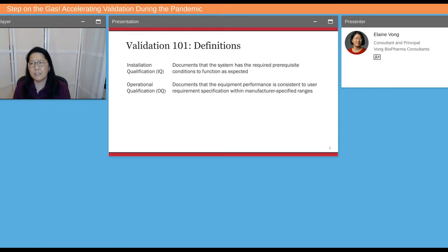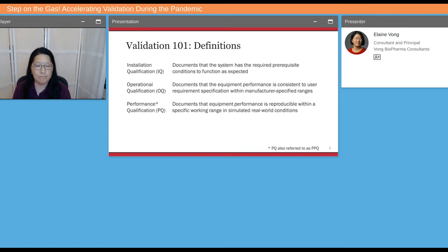It's always a good idea to ensure that the equipment you've purchased works as designed, or that you get what you're paying for in terms of capability of the equipment. Later, if you don't do your operational qualifications at the limits of the manufacturer-specified ranges, and someone wants to use it at those limits, they're going to have to requalify because you did not cover the full range. So that can just save some time down the road.